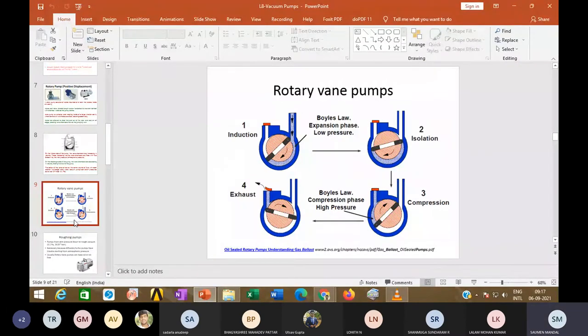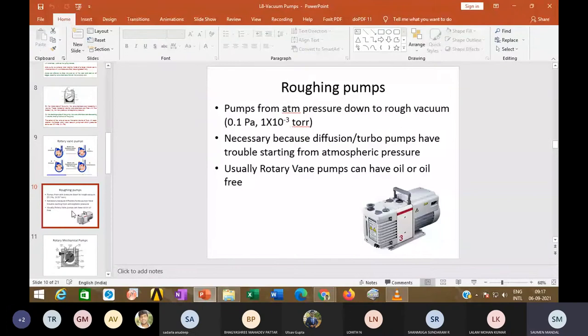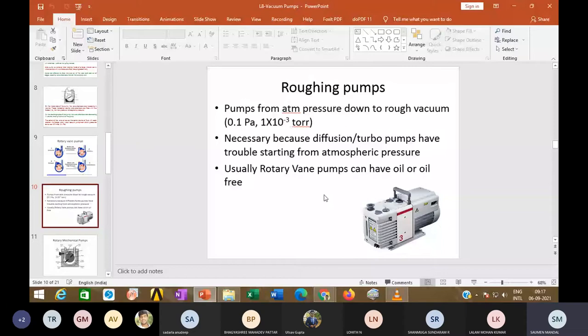The rotary vane pump is the roughing pump, bringing pressure down to rough vacuum — about 0.1 to 10^-3 torr. This is necessary because diffusion and turbo molecular pumps cannot start from atmospheric pressure. These pumps can be oil-lubricated or oil-free.